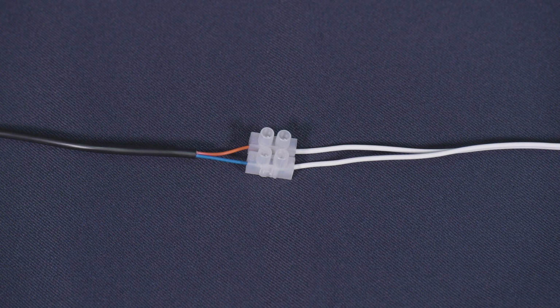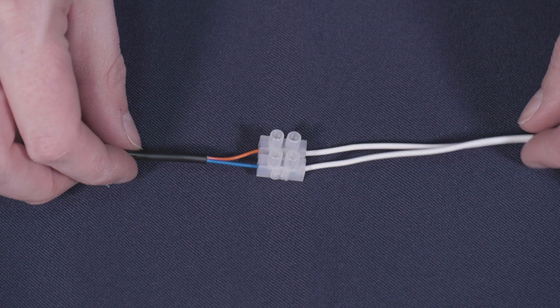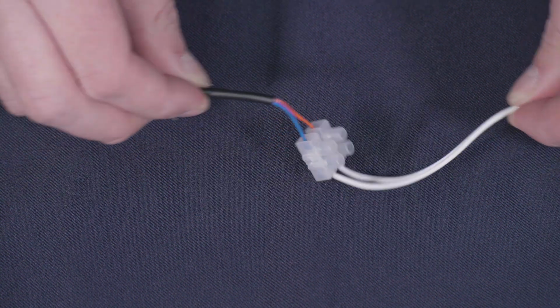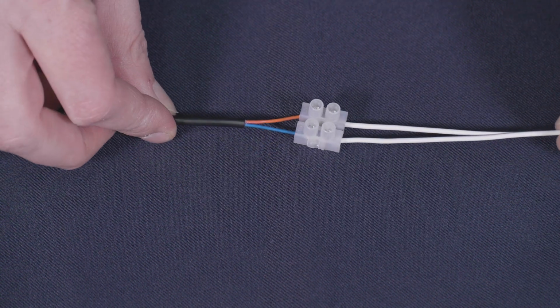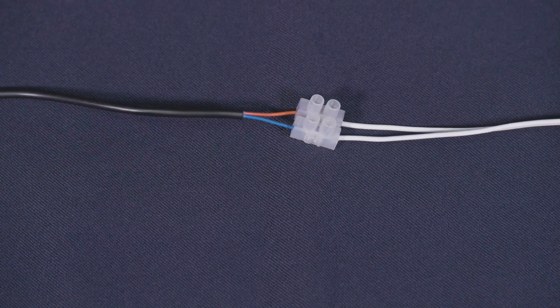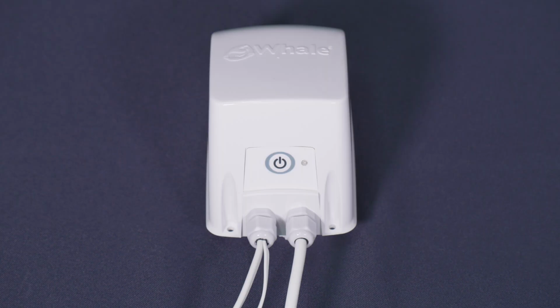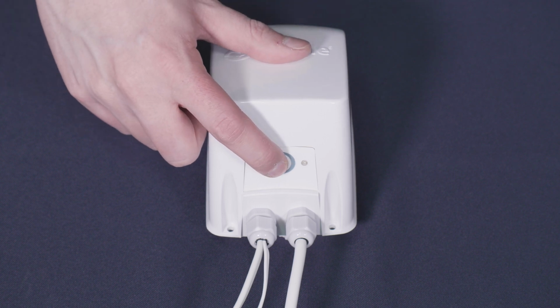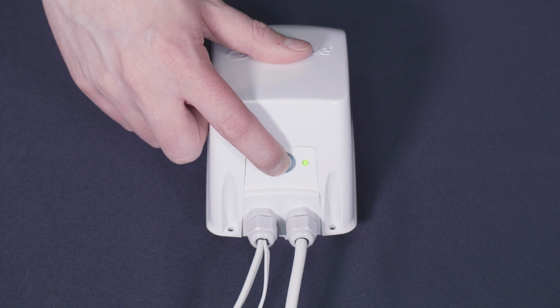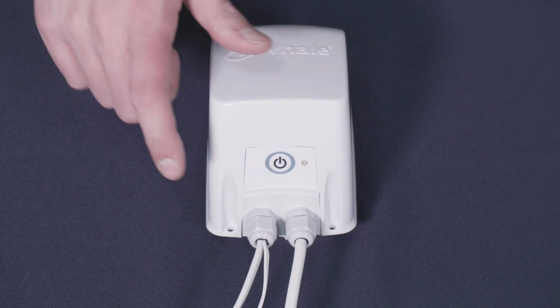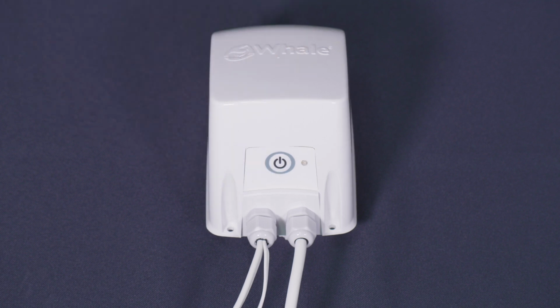Before looking at potential issues, please carry out some basic checks. Things to check include ensuring all wiring is undamaged and all connections are secure, also that no fuses have blown, and that power is getting to the transformer or that power has not been turned off. A quick and easy way to check if power is getting to the transformer is to press and release the white test button on the transformer. The LED should illuminate green, and the pump should start for around 30 seconds. If this operates correctly, then the issue lies with the signal being received by the transformer from the flow switch.